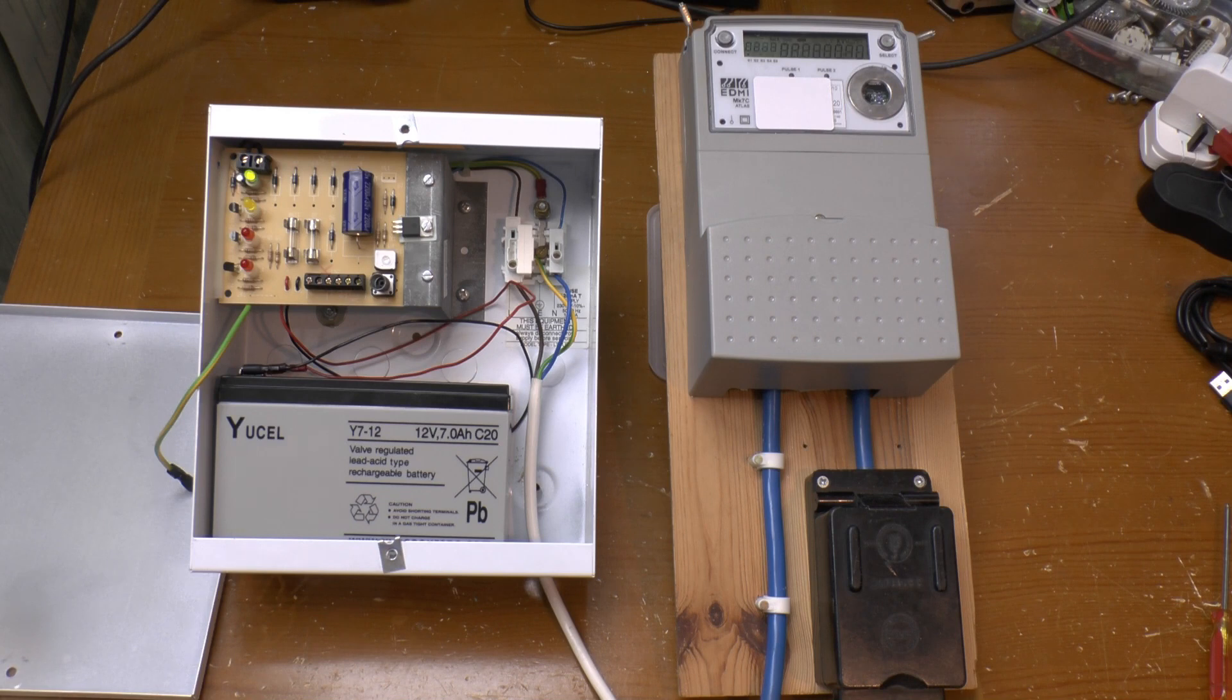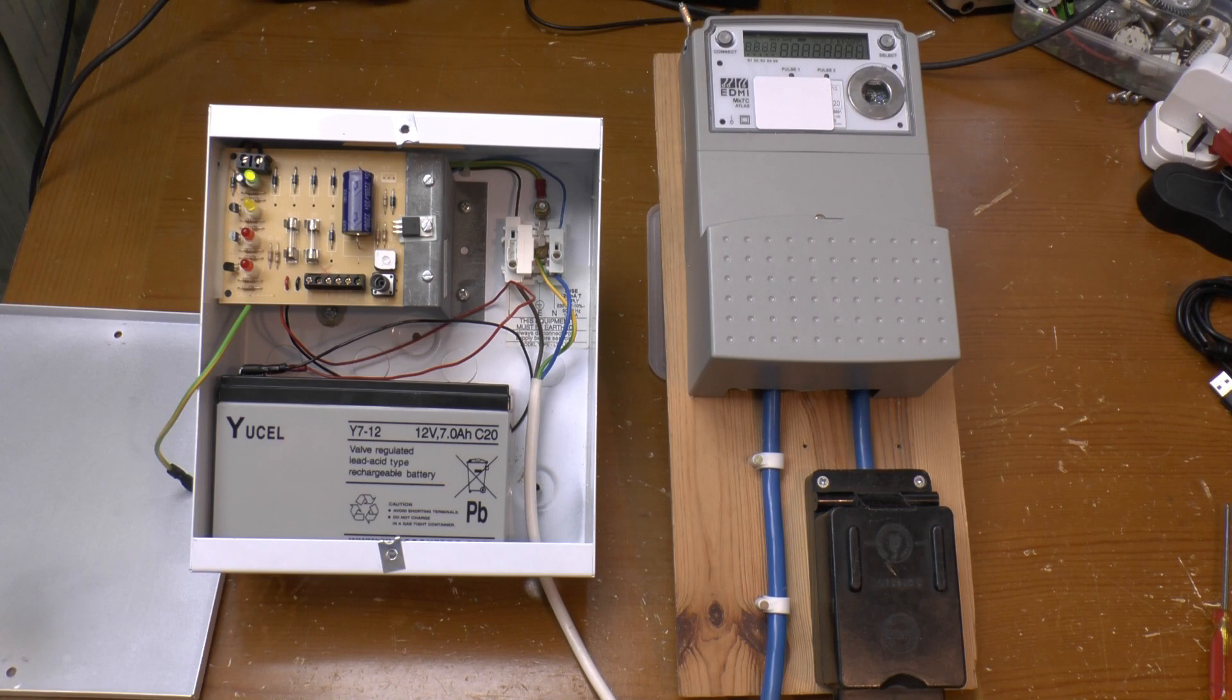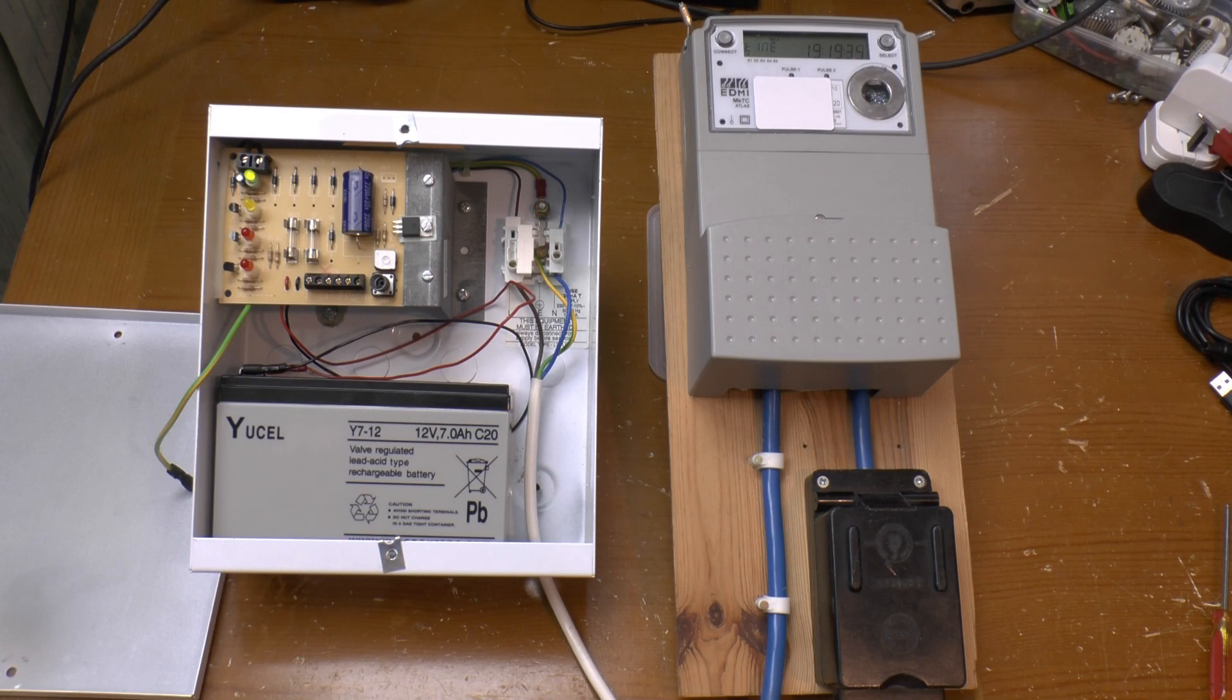There are 24 volt fire alarm power supplies which actually put out 27.6 volts, but this is a 12 volt intruder alarm model which is actually rated for 13.8 volts and in this case puts out 13.6.